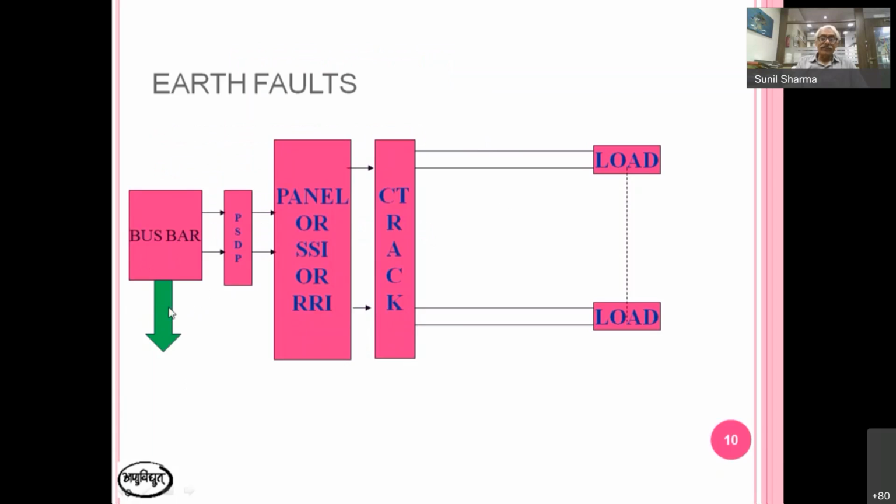If it does not exist here and a fault leakage becomes established here, the condition remains the same and it will work. And ELD also shows you a red light. So this condition was previously unnoticed and cannot be seen by any instrument. ELD shows it, and we have found this: 60% of busbars are leaky, whether it is their IPS channel, their charger, their battery bank, whatever it is, they are leaky.